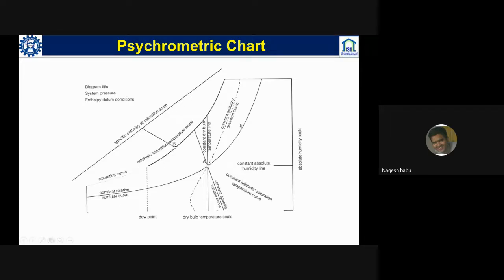In a typical psychrometric chart, on the y-axis we have the absolute humidity scale, and on the x-axis we have temperature, that is dry bulb temperature. If we move on the x-axis towards the left side, we are reducing the temperature. So whenever we design a particular system, we always try to move towards the left, so that we reduce the temperature to meet the cooling load, and also come down so that our humidity requirements are met.